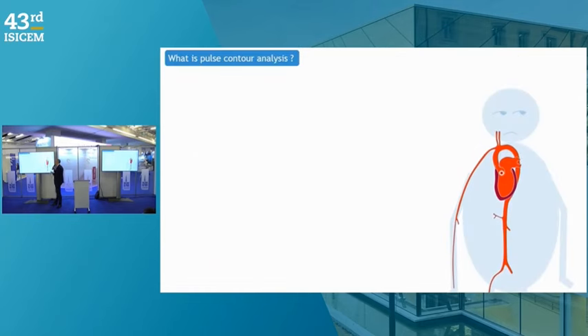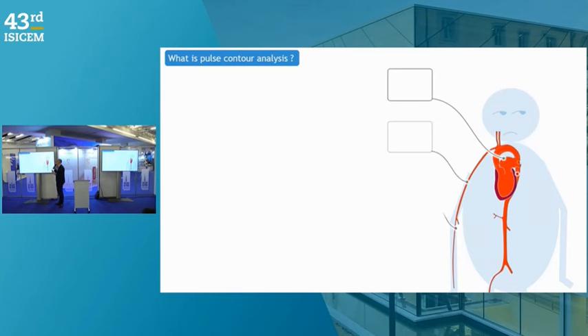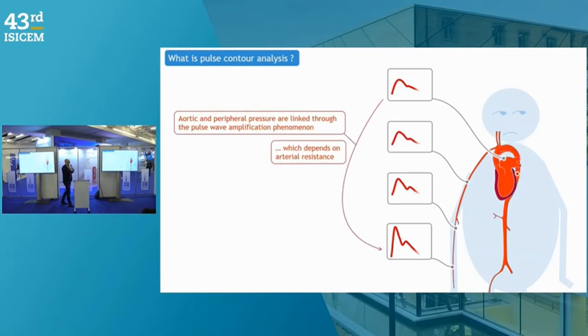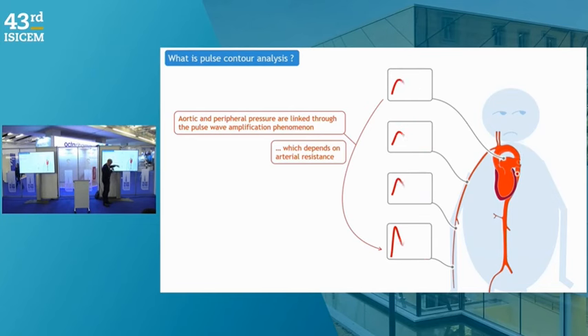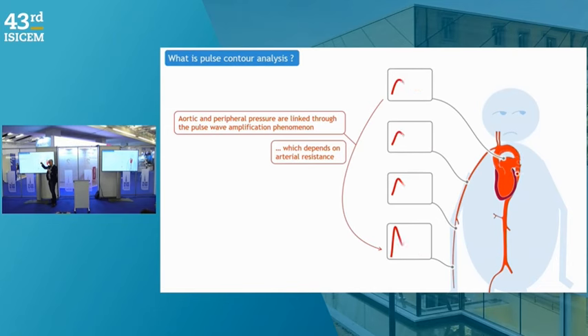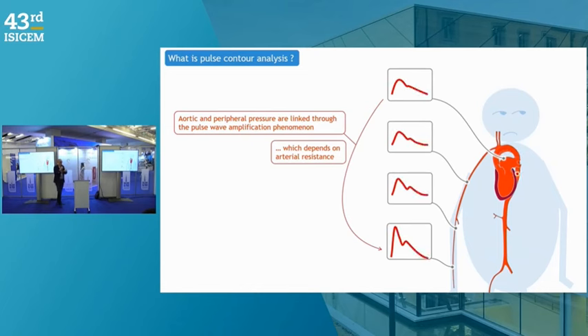Something else must be kept in mind. What we measure at the bedside is not the aortic pressure — it is the peripheral pressure. You know from physiology that the amplitude of the blood pressure signal is amplified from the central aortic level to the peripheral level. So the relationship between waveform amplitude and stroke volume that holds at the aortic level is not true at the peripheral level. This pulse wave amplification phenomenon depends on arterial resistance.